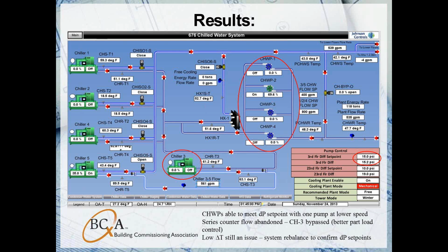And it was hours of tracing pipes and climbing and testing to find this valve that Mark's talking about. But you're doing sort of forensics here, like, okay, where are we losing the water? It's going somewhere. So I just want to share that part of what Mark's pointing out is tips: these are things we saw that were a problem, and that's something you should be looking for in your projects. If you see that DP not met, well, why? If the pumps are moving and the DP is not satisfied, something's wrong in between.